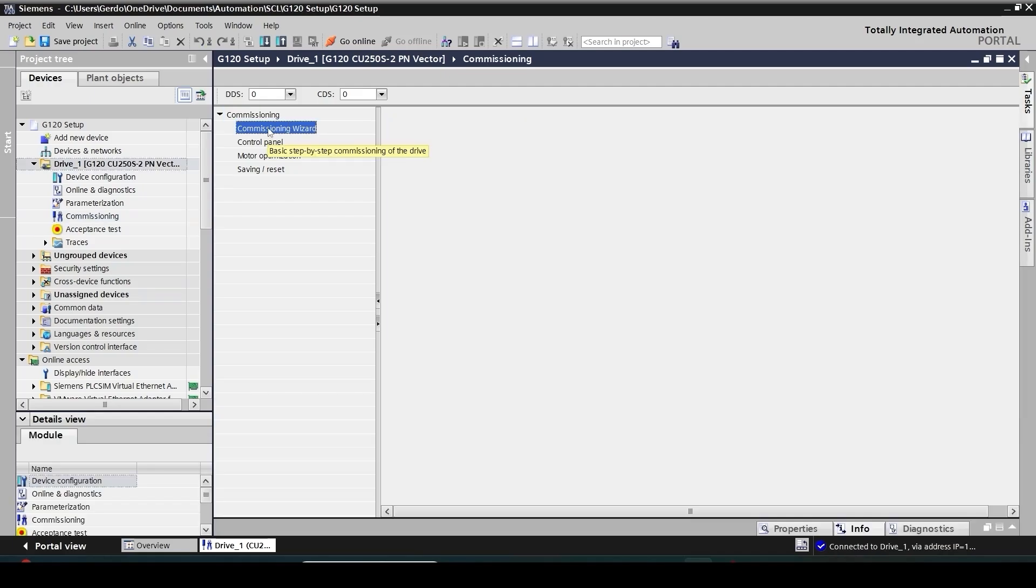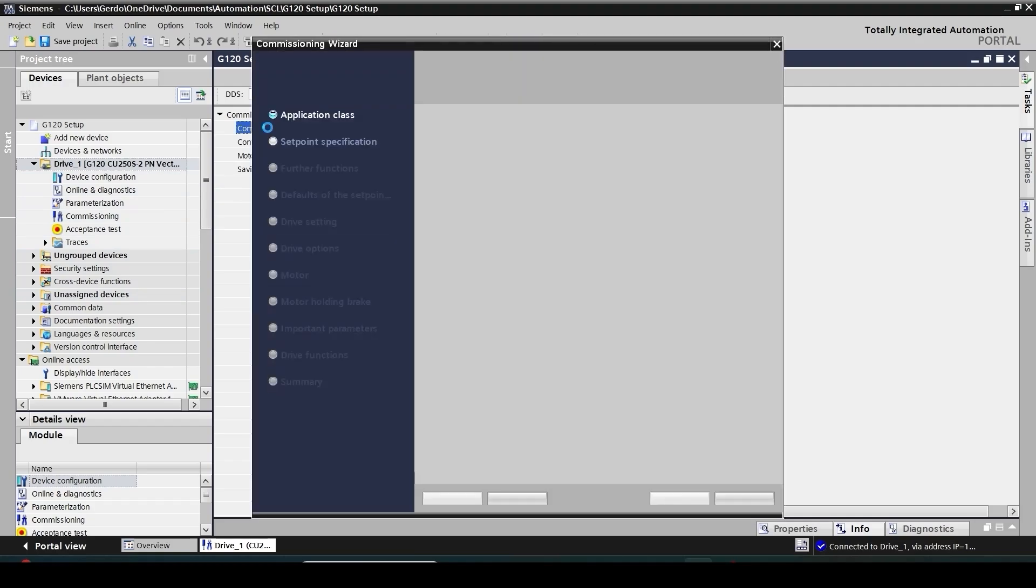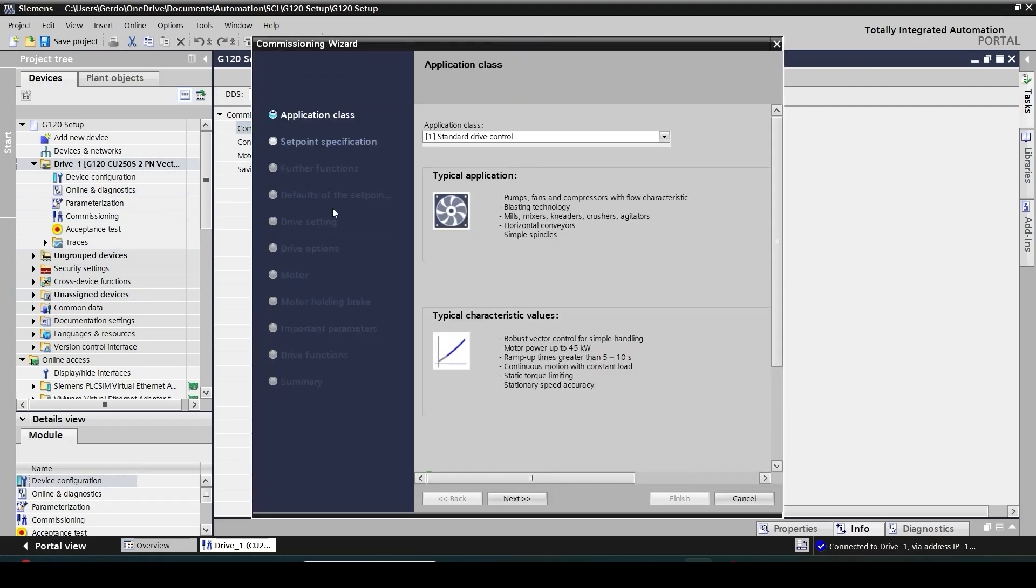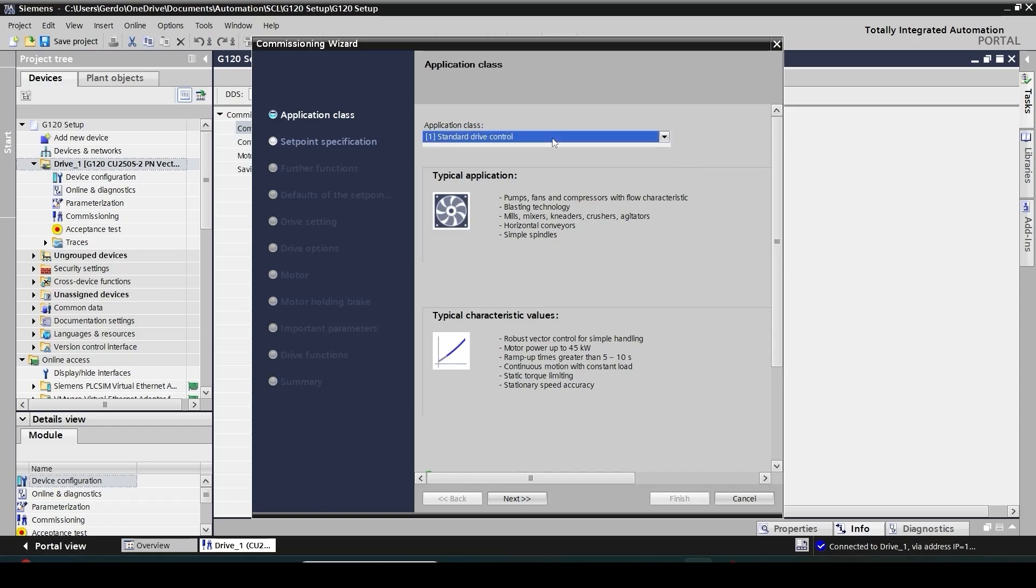I'm going to double click here to open the commissioning wizard. This commissioning wizard will take me through the necessary steps to configure my drive properly. Siemens drives are offered with many options. In each step it asks me some questions that I would like to configure my drive. In the first window, application class, it's just a simple standard one which could be like pump or fan.